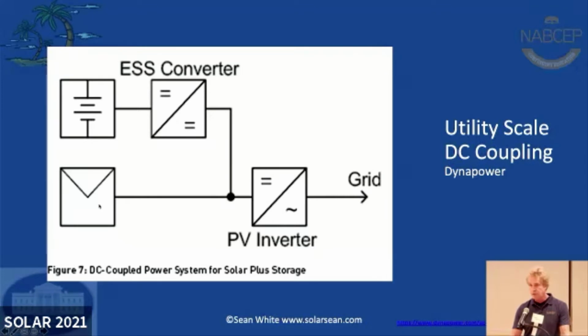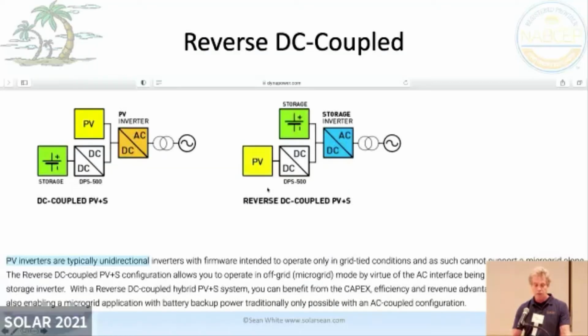This is where utility scale typically uses DC coupling. They take a PV inverter, it's not an energy storage system inverter, and then they modify that. And on the DC side of that PV inverter, they get this battery to go just the right voltage to work with that PV inverter on the DC side. Another thing though is a PV inverter is a one-way thing. You can't really charge the battery from the grid with this. So that's another drawback, and they could design it differently so that the inverter could charge the battery from the grid. This is called reversed DC coupling. We put the DC to DC converter with the PV, and we have an energy storage inverter, and that way we can charge the battery from the grid if we need to. So that's just a different type of DC coupling.